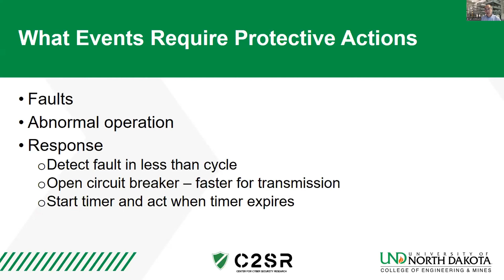And then to provide redundancy, there are overlapping zones of protection. So for this transmission line, for example, there's going to be backup protection. If this breaker fails, or this breaker fails, or the relay fails, something else is going to send a command to make sure that you isolate that, but you isolate a little bit more of the system. There are often going to be redundant relays.